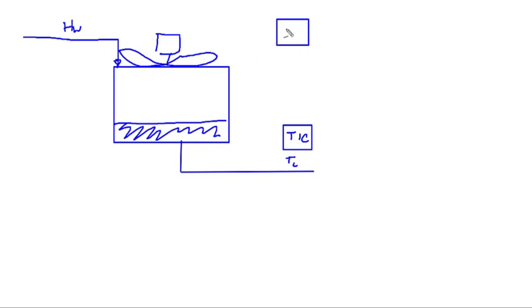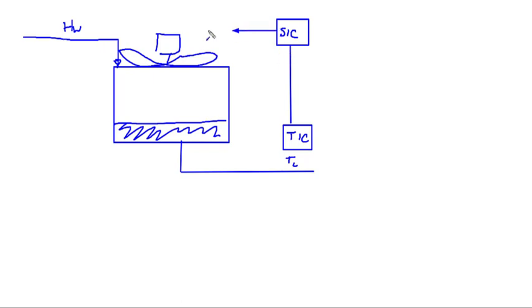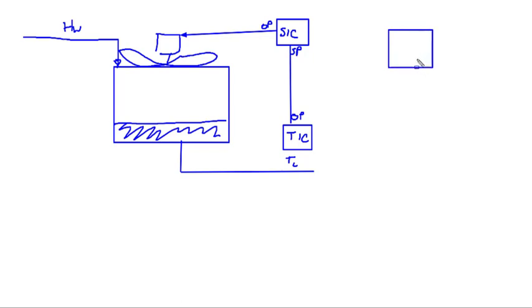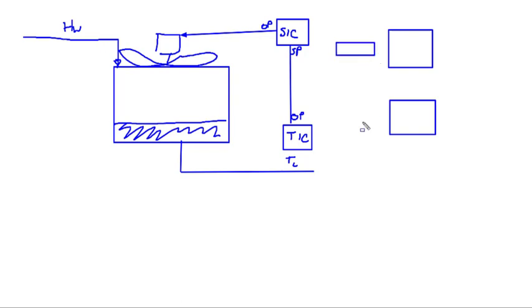So this is an SIC and this went to there and this went to the PLC. This is its output which becomes a set point to the SIC, the speed control, and the output of this became the set point to the VFD. In the DCS configuration on a Yokogawa system, we had PID here, one PID, second PID, input channel to the first PID which was the temperature, input channel to the second PID which is the feedback of the rotation of the speed.